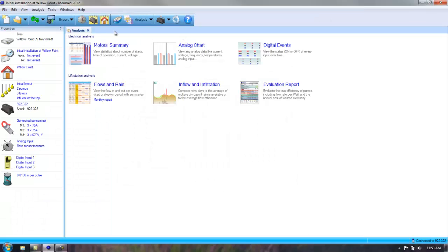and now you notice I have a motor summary, analog chart, digital events, flow and rain, inflow and infiltration, and evaluation report available to me, but I haven't collected any data from the device. One thing I want to mention, I was making a generic station. Now once I got out to the station, I found out 2 things. Number 1, my levels weren't correct. And number 2, the 75 amp clamps were not large enough. I needed 300 amp clamps for this duplex station because the motors were, say, 75 horse motors.